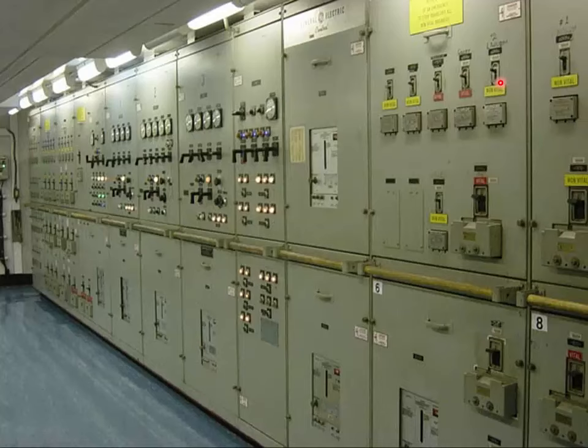If there is an overload, they will pop to the middle, and the middle position gives you an indication that it is tripped. And to reset, you pull down to the open position, and then you manually lift it back up again. If you ever have a tripped breaker and you pull it down to reset it and then set it back to closed and it immediately pops out, do not energize that breaker again. That means that it's a severe overload. It's doing its job and it's tripping.